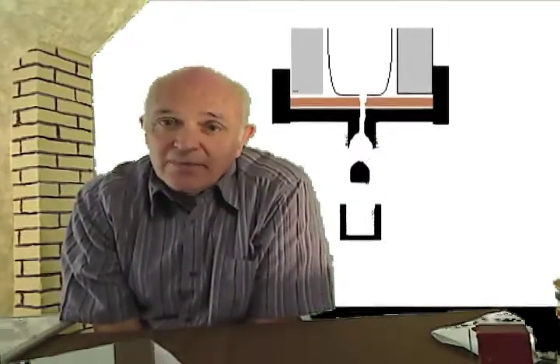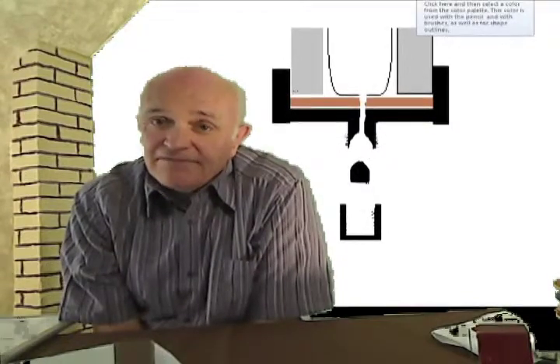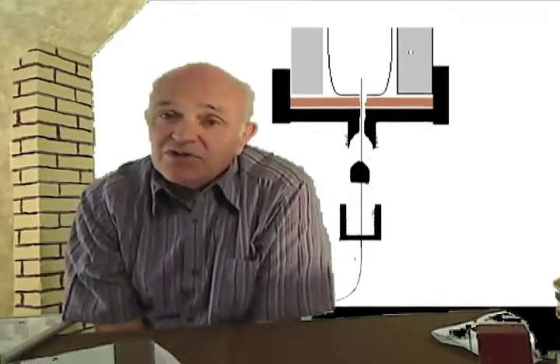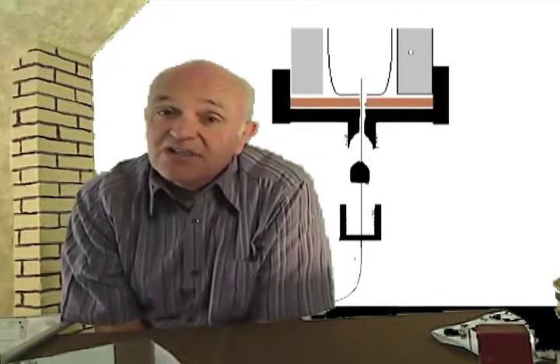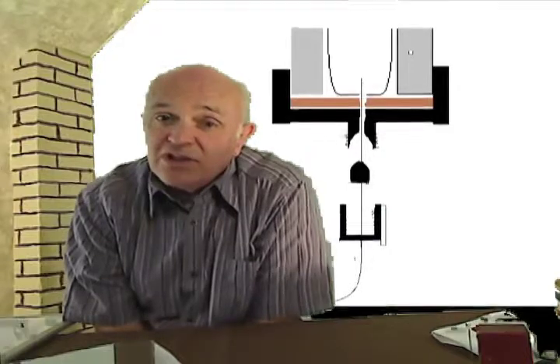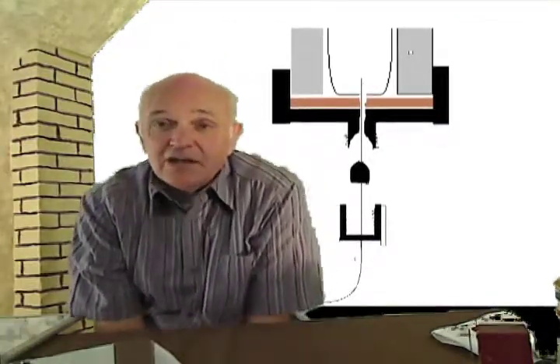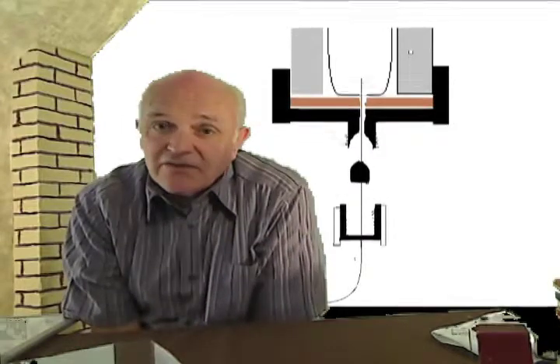Gas chromatography is all about time and temperature. The temperature of the oven goes up and down as part of its programming. The temperature of the injector should stay the same. You need to keep these temperature zones separate. The way to do it is to be sure to put the little cover back on. There's a little cover that goes up around the injector. Make sure that cover is put back on.